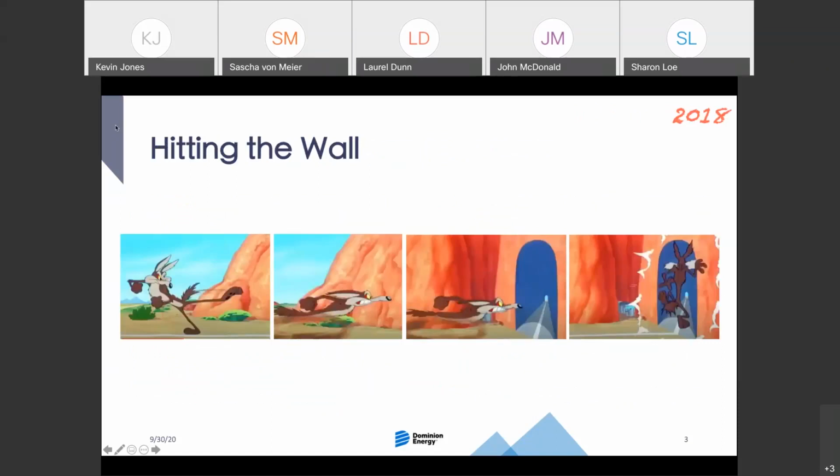We did all these really great things, and we had all this data, and we'd made a lot of assumptions about how we were going to manage it and how we were going to use it that had really never been stress tested. And what ended up happening was that we found out very quickly that our enterprise data historian just wasn't up to the job of not only visualizing and analyzing our synchrophasor data, but sometimes just ingesting it.